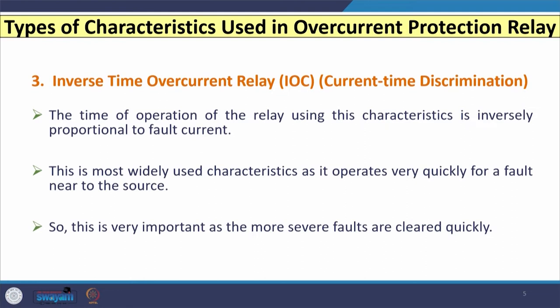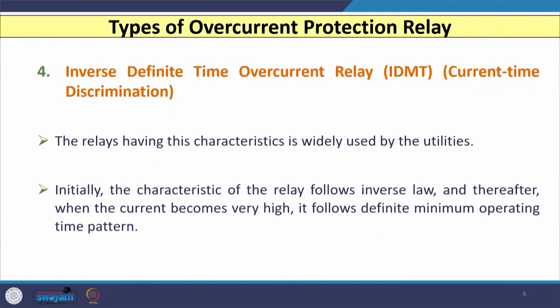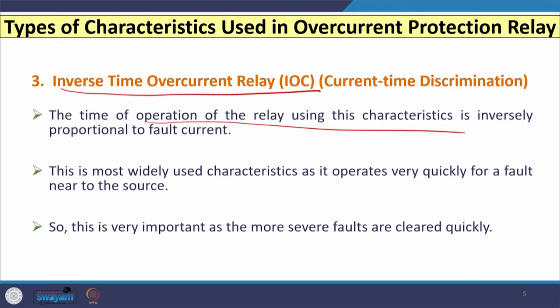Combining both current discrimination and time discrimination gives us the third type of characteristic: the inverse time overcurrent characteristic. In this case, the time of operation is inversely proportional to the magnitude of fault current — higher fault current means lower operating time, and vice versa. The most widely used sub-characteristics under inverse time are normal inverse, very inverse, and extremely inverse. As we move from normal inverse to very inverse to extremely inverse, the slope of the characteristic curve becomes steeper, so the user must select the most suitable characteristic for the application.